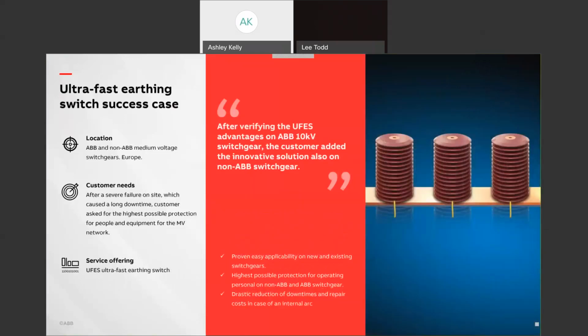This next example is of a data center with a combination of both ABB and non-ABB medium voltage switchgears. In this request, the customer had a severe failure on site, and that had led to a catastrophic system-wide shutdown. The customer requested for the highest possible protection for his people, his assets, all on his medium voltage network. Again, the service team locally provided and installed and commissioned ultra fast acting earth switches. After validation of the advantage of these ultra fast acting switches, this site then rolled out this innovative solution across the non-ABB switchgear as well as their ABB switchgear on site.